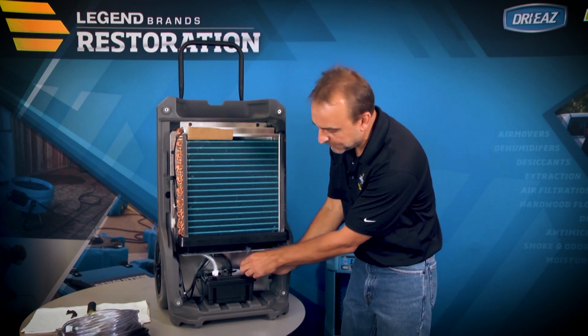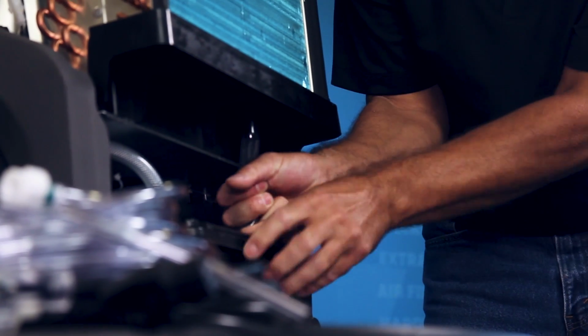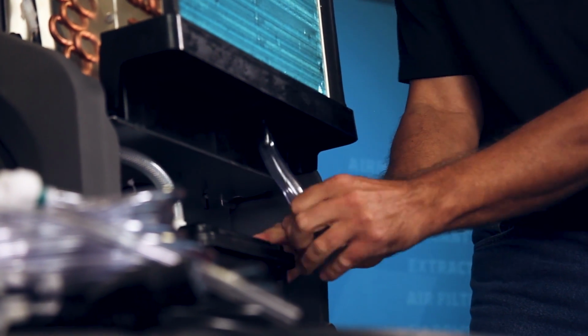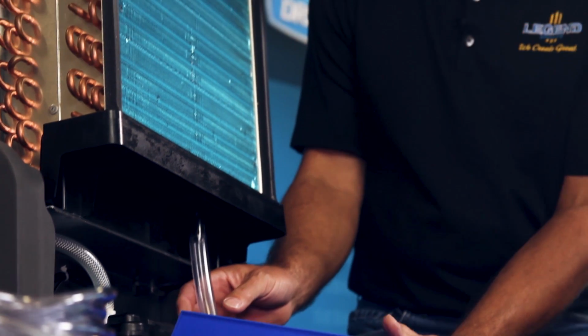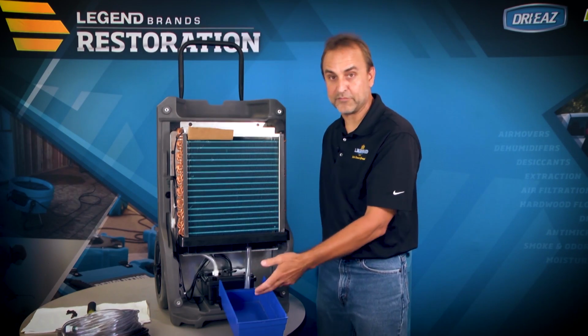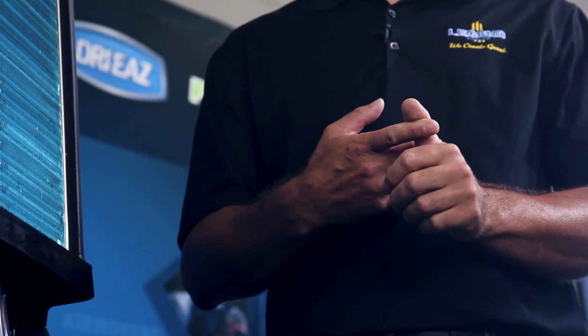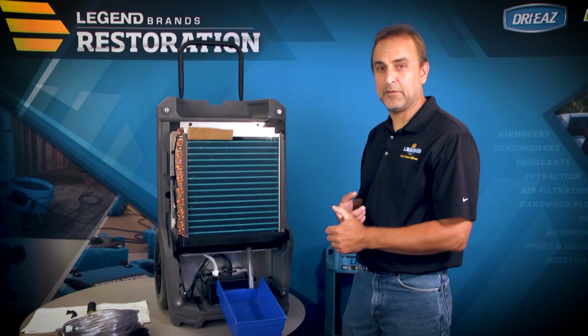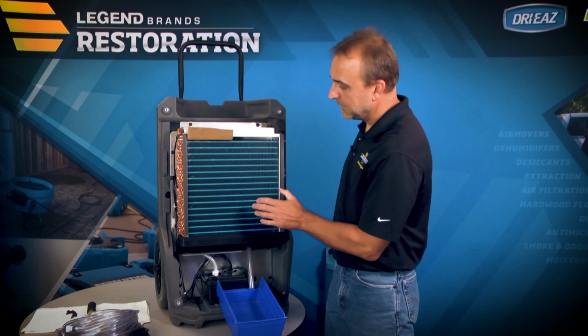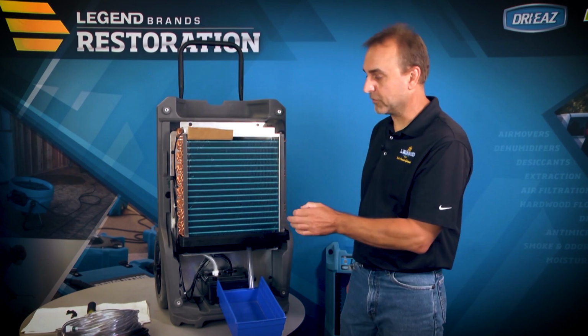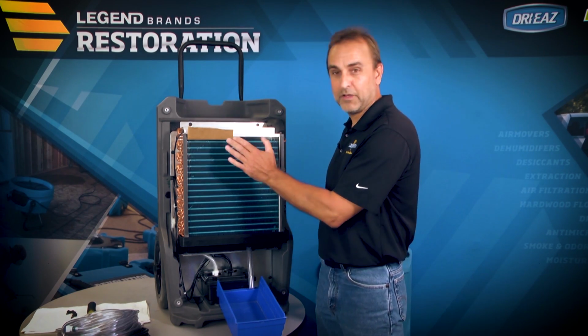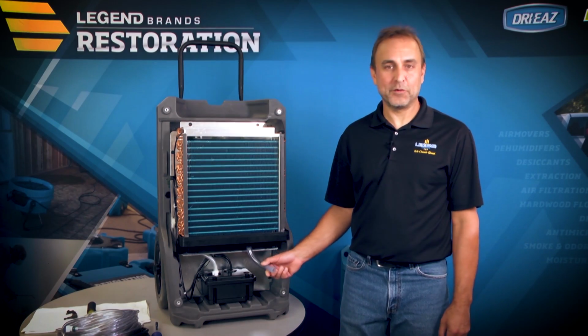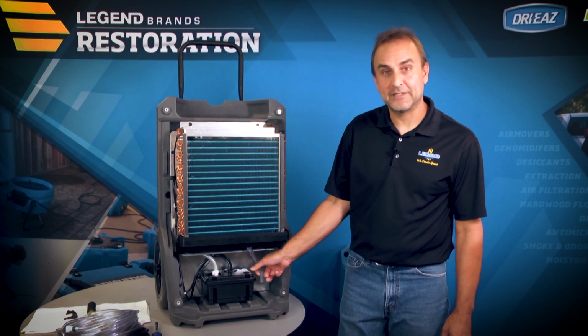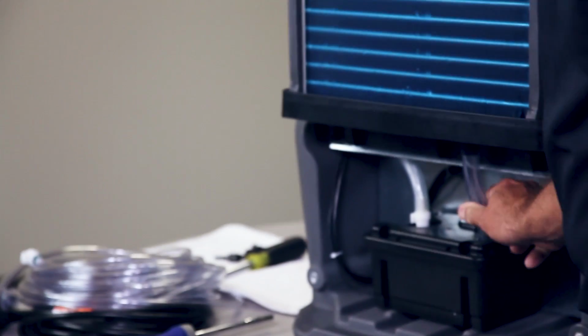When doing this in the shop, we'll usually remove the condensate pump input line from the pump and place it into a collection container to collect the residue and debris that run off of the coil. When using coil cleaner, make sure to reference the SDS and wear appropriate PPE. Also, on the instructions of the coil cleaner, it will let you know how long to let the coil cleaner dwell and if it is a self-rinsing. After cleaning the coil assembly, make sure you put the condensate pump input line back into the pump.